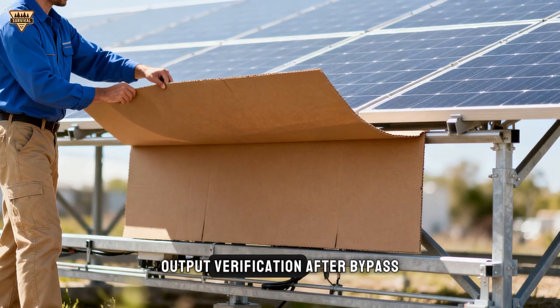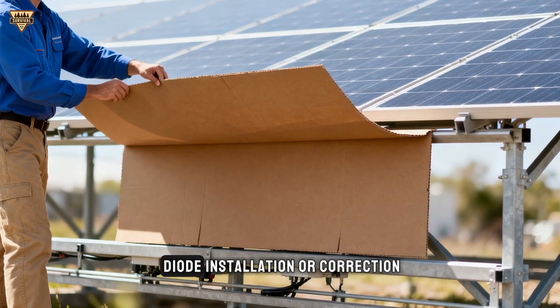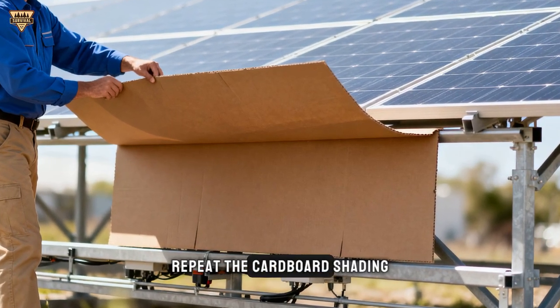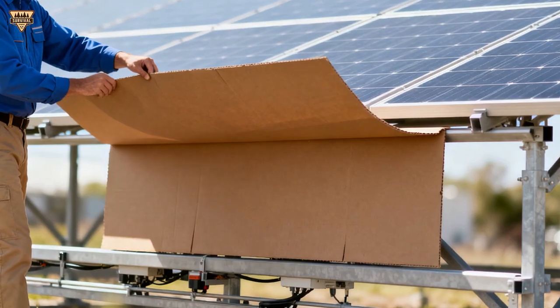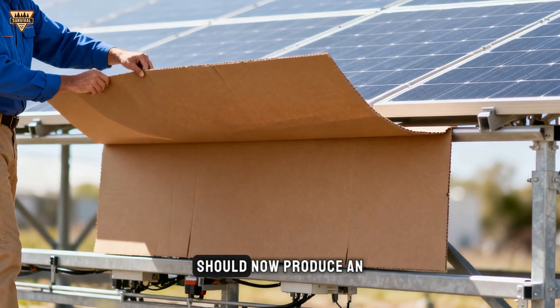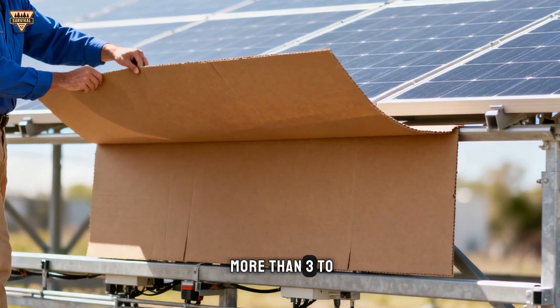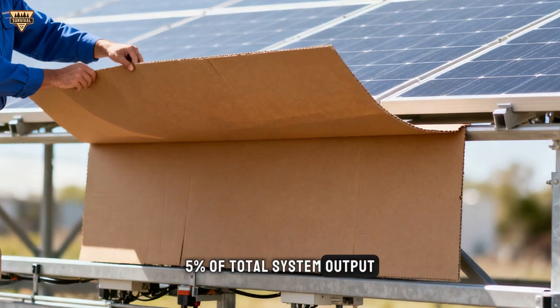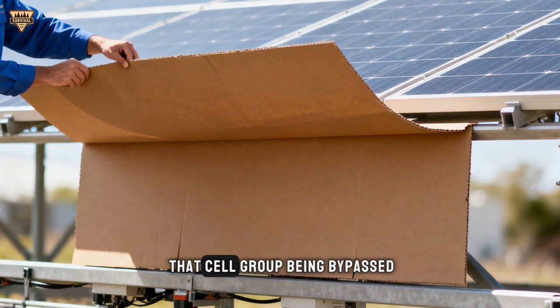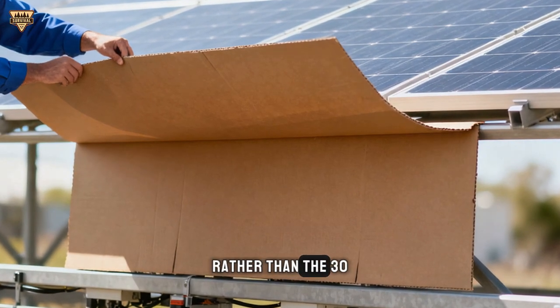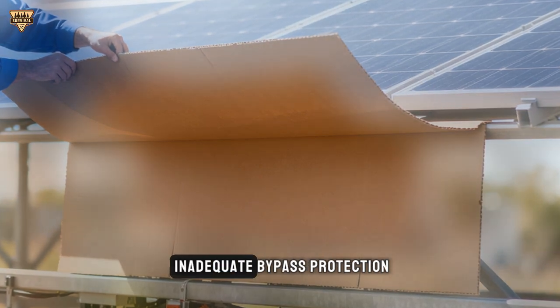Output verification. After bypass diode installation or correction, repeat the cardboard shading test from step 1. Covering 1/3 of one panel should now produce an output drop of no more than 3 to 5% of total system output, the proportional loss from that cell group being bypassed, rather than the 30-40% cascade loss from inadequate bypass protection.